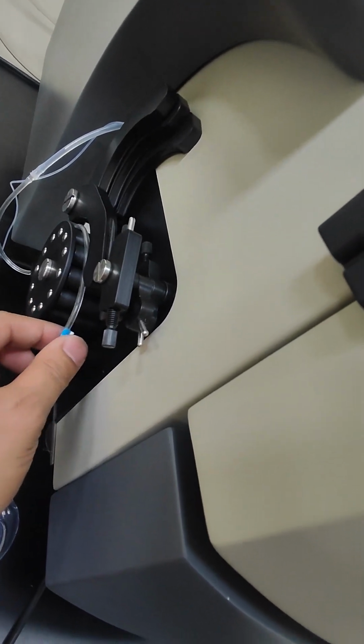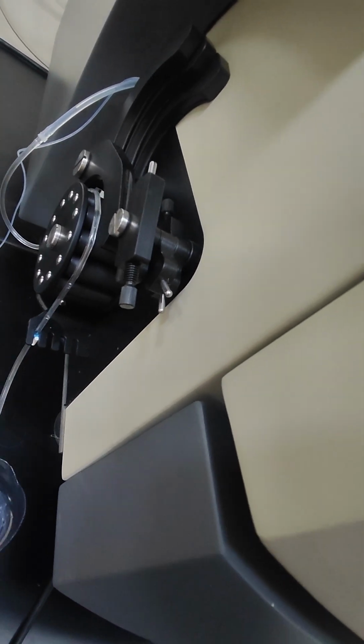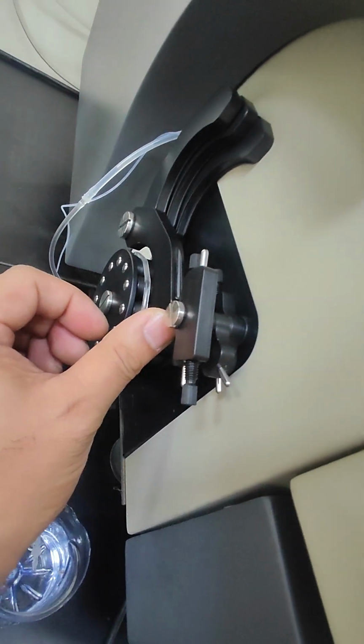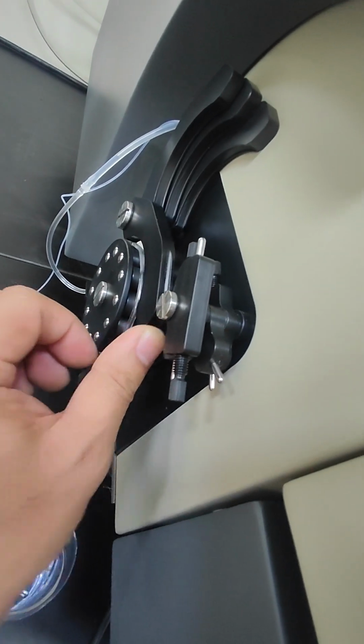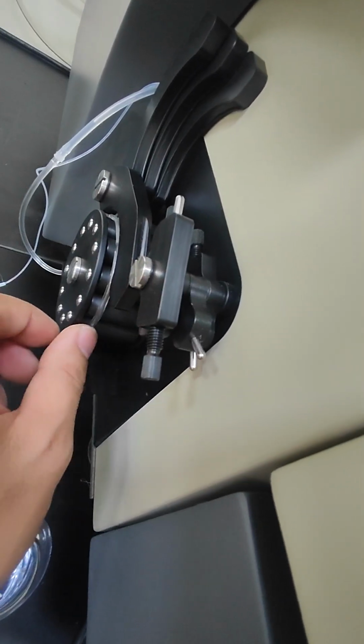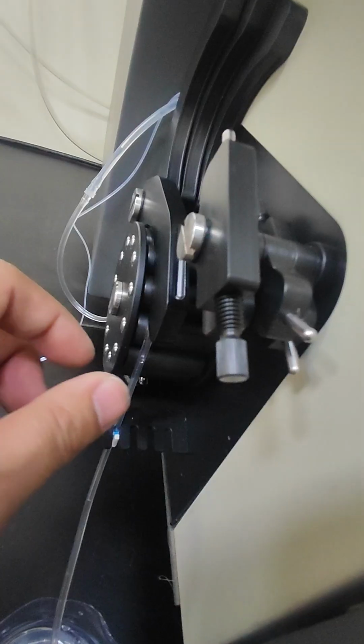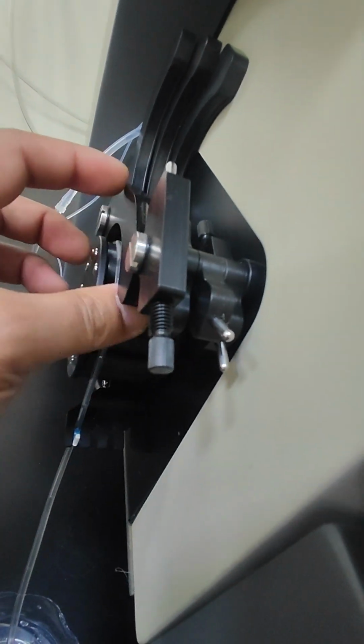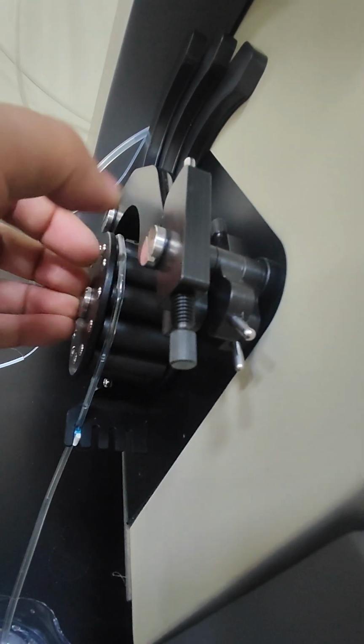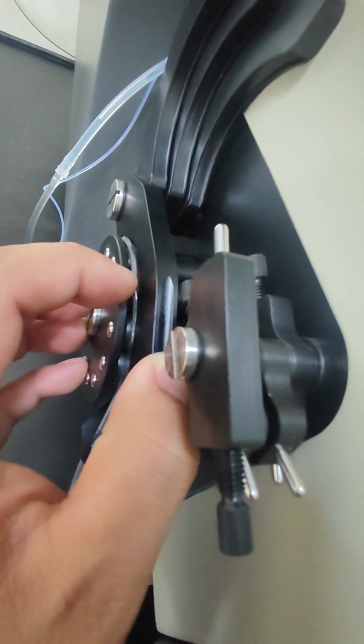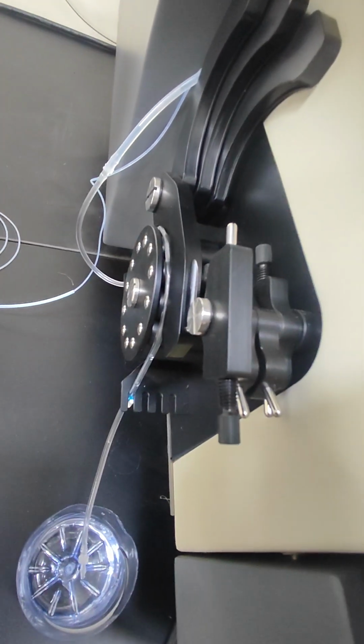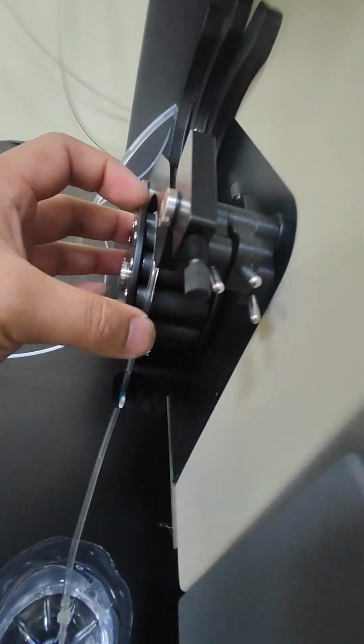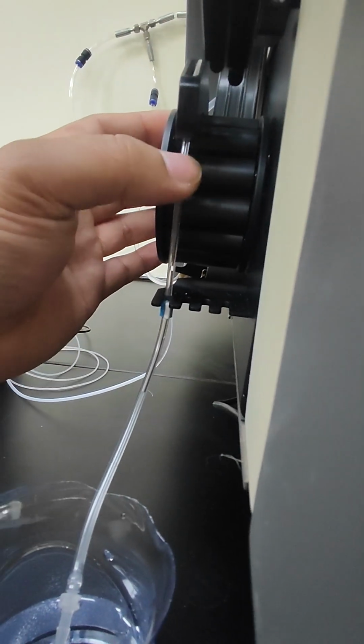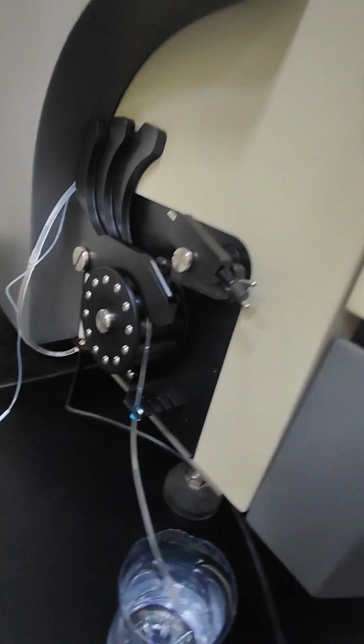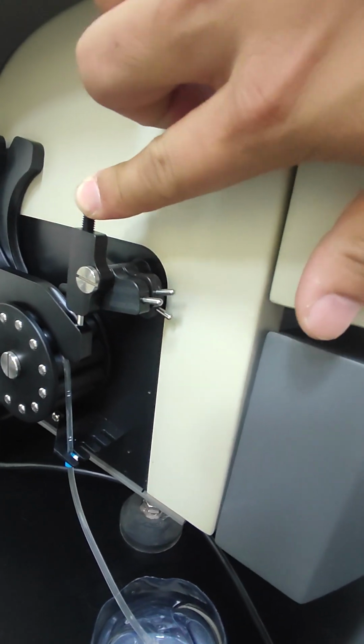Okay, now for the pump tube, we can install it, and we only install the first one. When we press down the press block, we need to make sure the tube is at the center. It should not be like this. You cannot press half of the tube. It will damage the tube. So we need to put it at the center. After putting it, press this down.